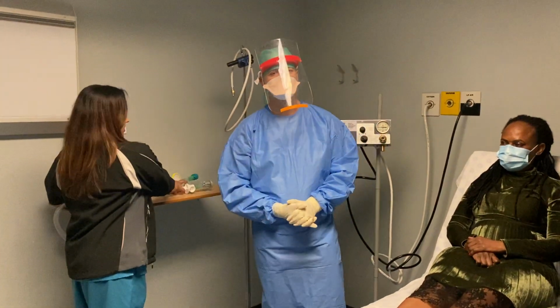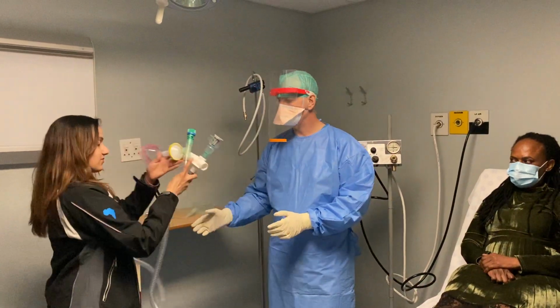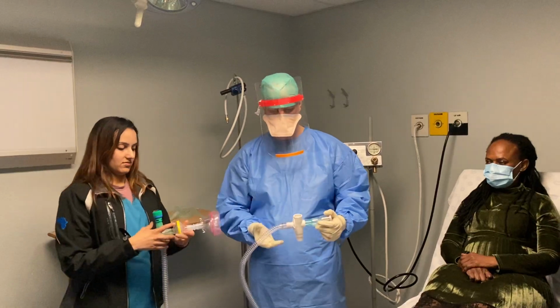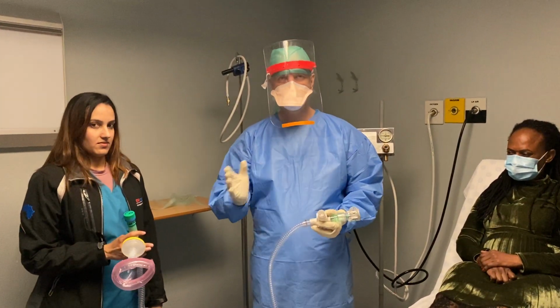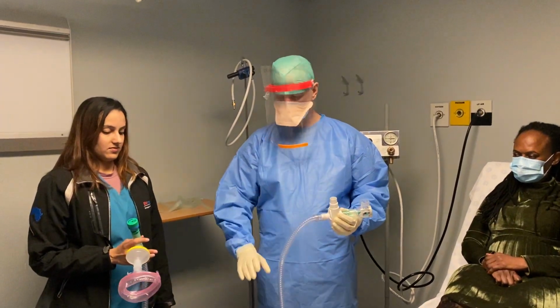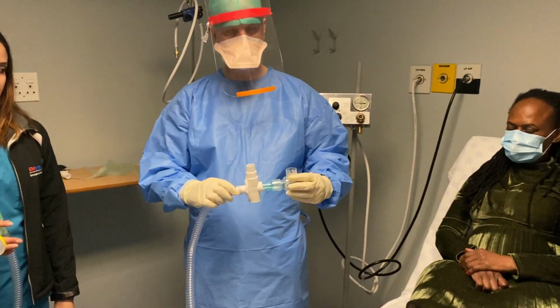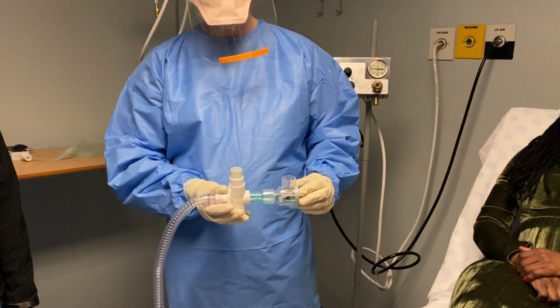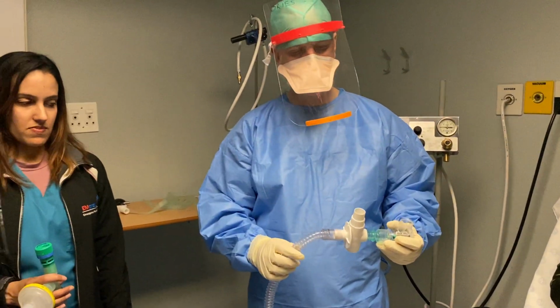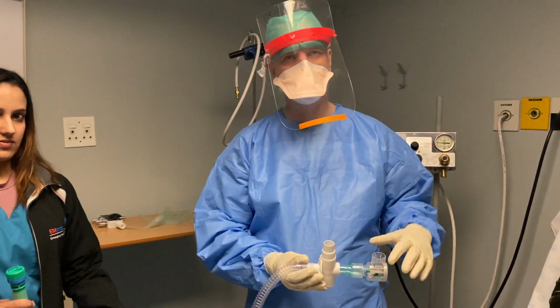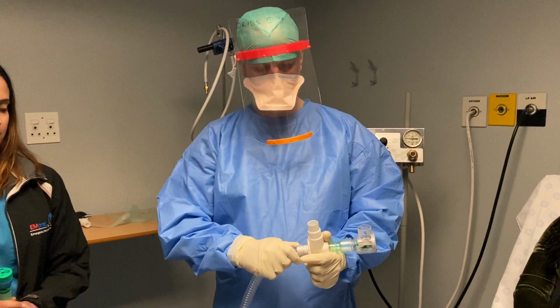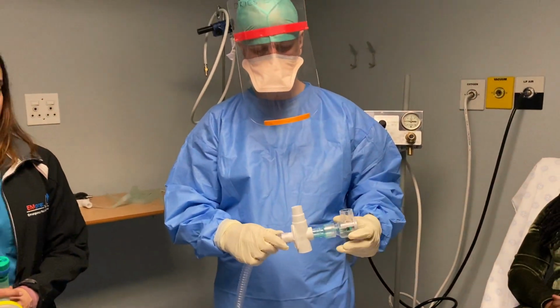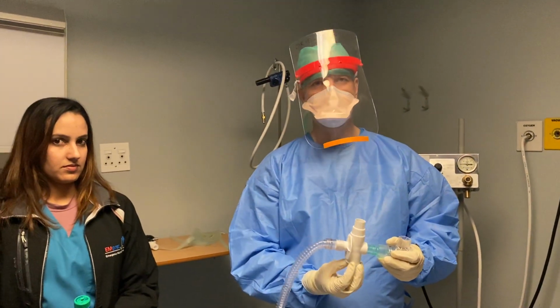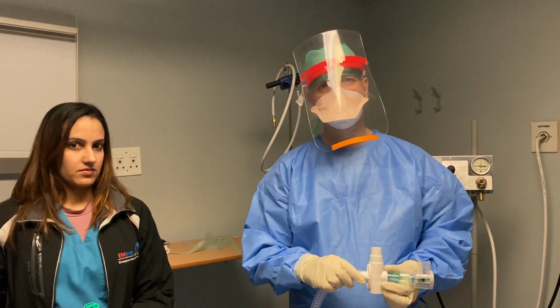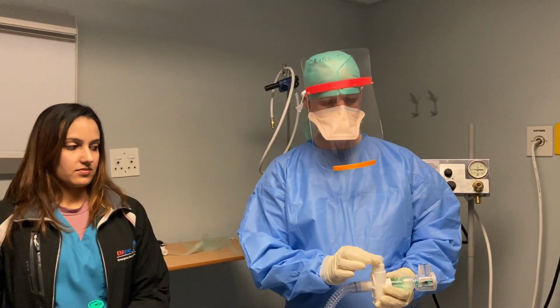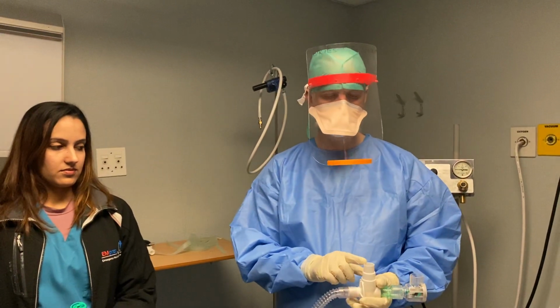So Prof is going to talk to us about the circuit that we use. So I'm going to start off by talking about the circuit that we will be using for all three of these devices. We'll be using the same circuit for all three of these non-invasive ventilation devices. This is a simple circuit, and it starts off on this side with a pop-off valve. The pop-off valve is just a valve that is designed to ensure that the pressure inside the circuit doesn't exceed safe levels, so it will open up when the pressure increases beyond a certain pressure. The next valve is the anti-asphyxia valve, and that will allow the patient to entrain room air into the circuit to ensure that the patient always has an adequate supply of breathable gas. This connection here will be the connection that will be connecting to the three devices.